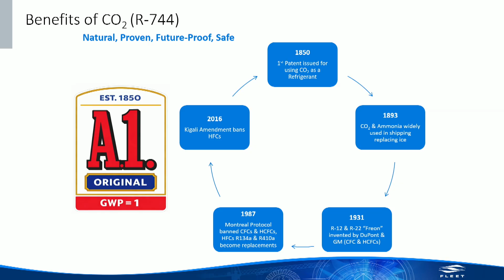The next thing to keep in mind is that cycle I explained is continuing on. Even the refrigerants we're starting to see today, 454B, R32, a lot of these A2Ls, are soon to be banned in New York State as well. Most of them are going to have a life until about 2034, but that's only about 8 years from now, and in some applications like VRF it's even shorter, 2030. So what's being installed today is almost already obsolete, whereas if you're using an A1 like CO2, it's been around since the 1850s and it's not going anywhere. So certainly something to consider—you have to really understand the implications of the refrigerant you're using in your heat pump.